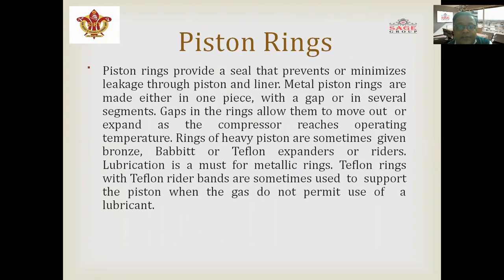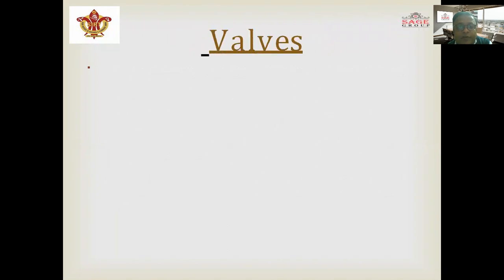Piston rings provide a seal to prevent or minimize leakage between the piston and the liner. Metal piston rings are made either in one piece with a gap or in several segments. Gaps in the rings allow them to expand as the compressor reaches operating temperature. Rings of heavy pistons are sometimes made with bronze, babbitt, or Teflon expanders or riders. Lubrication is a must for metallic rings. Teflon rings with Teflon rider bands are sometimes used when lubricant is not permitted.